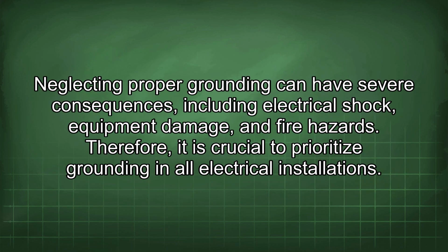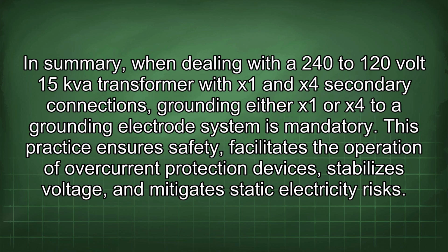Neglecting proper grounding can have severe consequences, including electrical shock, equipment damage, and fire hazards. Therefore, it is crucial to prioritize grounding in all electrical installations. In summary, when dealing with a 240 to 120 volt 15 kVA transformer with X1 and X4 secondary connections, grounding either X1 or X4 to a grounding electrode system is mandatory. This practice ensures safety, facilitates the operation of overcurrent protection devices, stabilizes voltage, and mitigates static electricity risks.